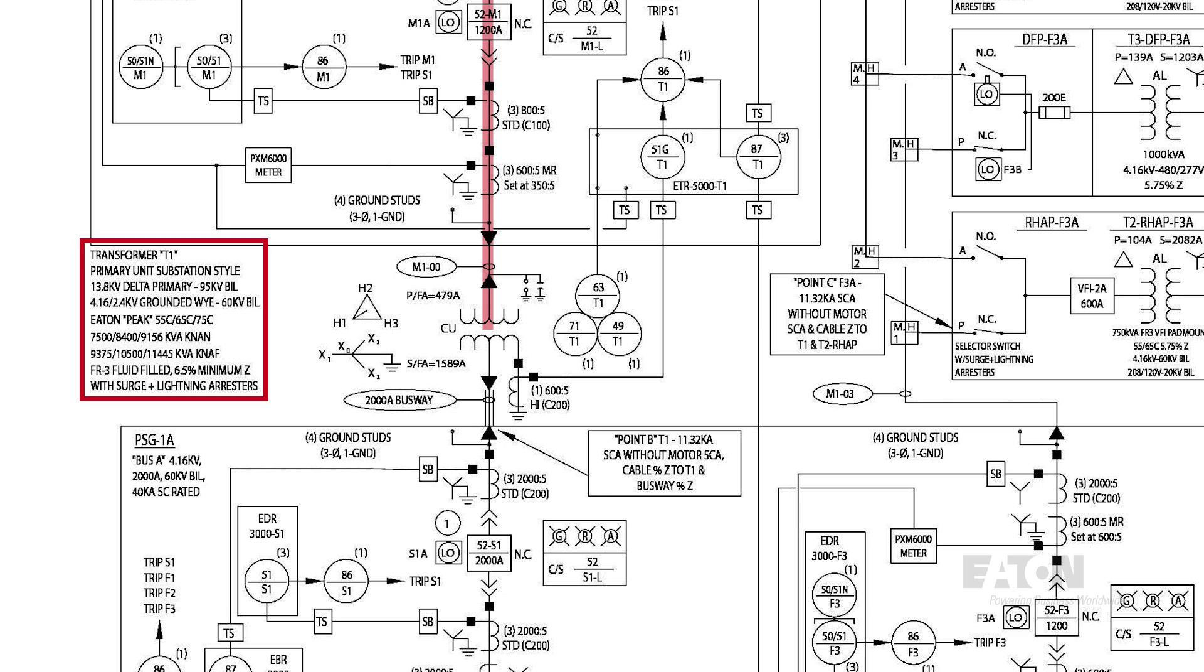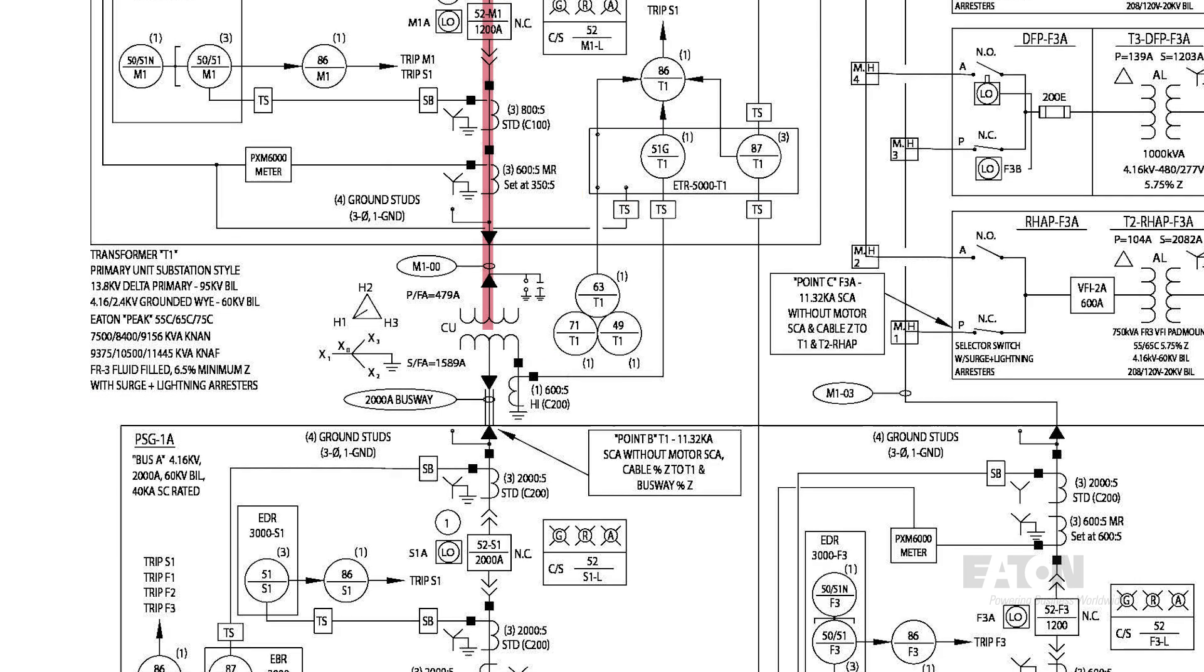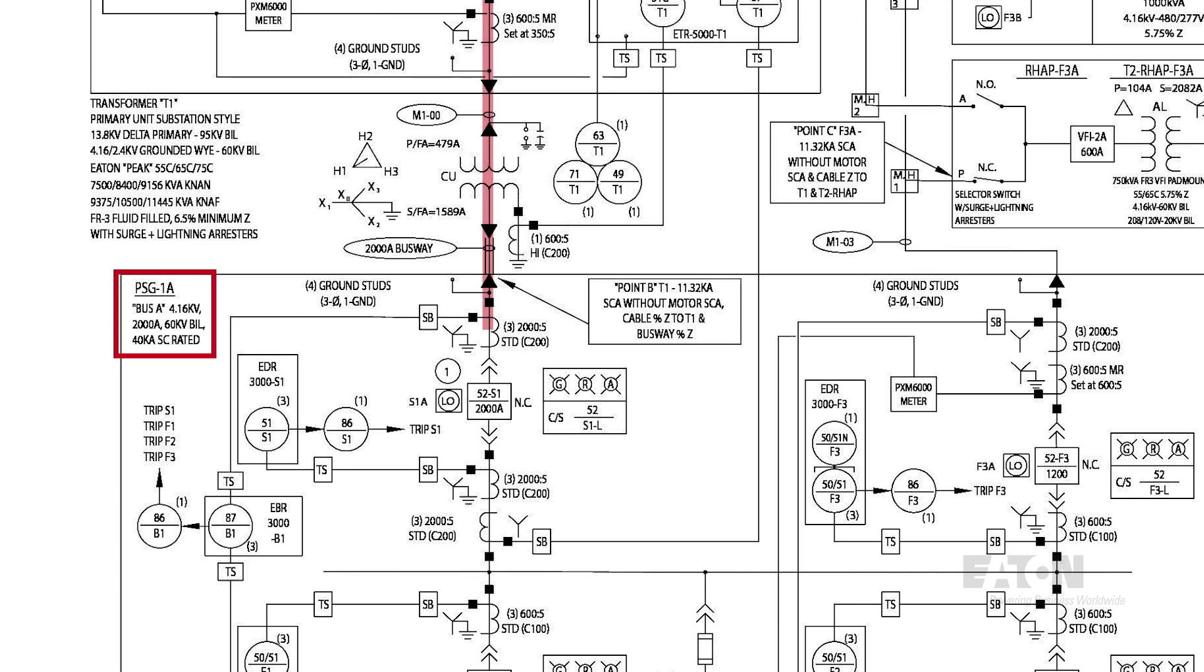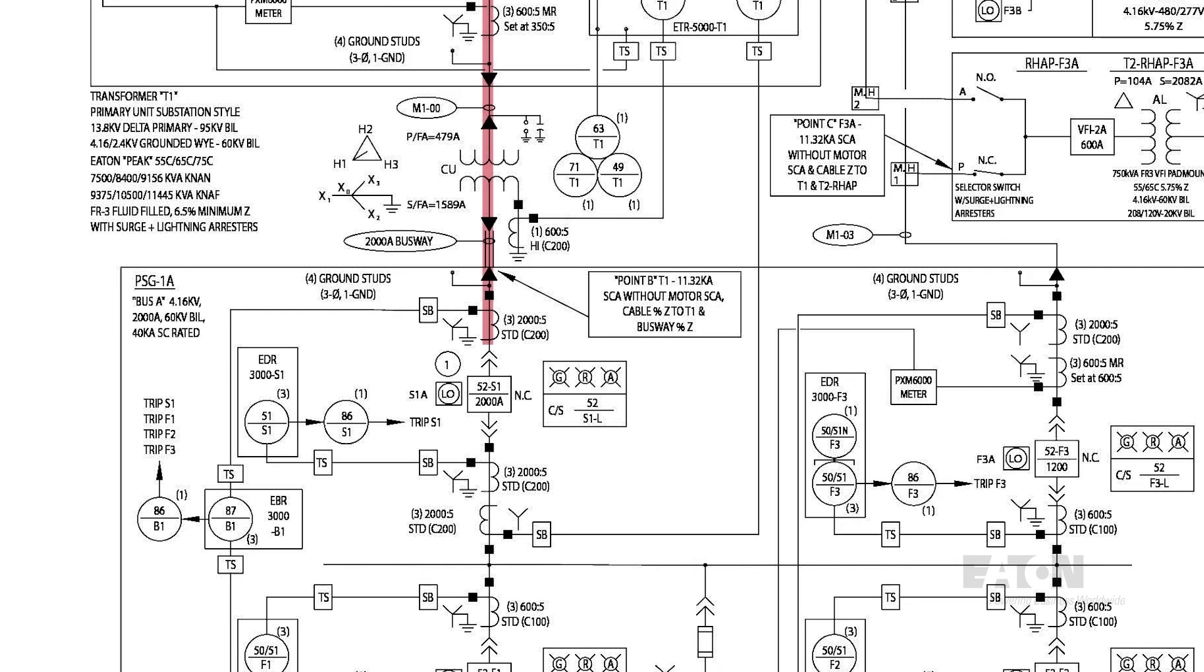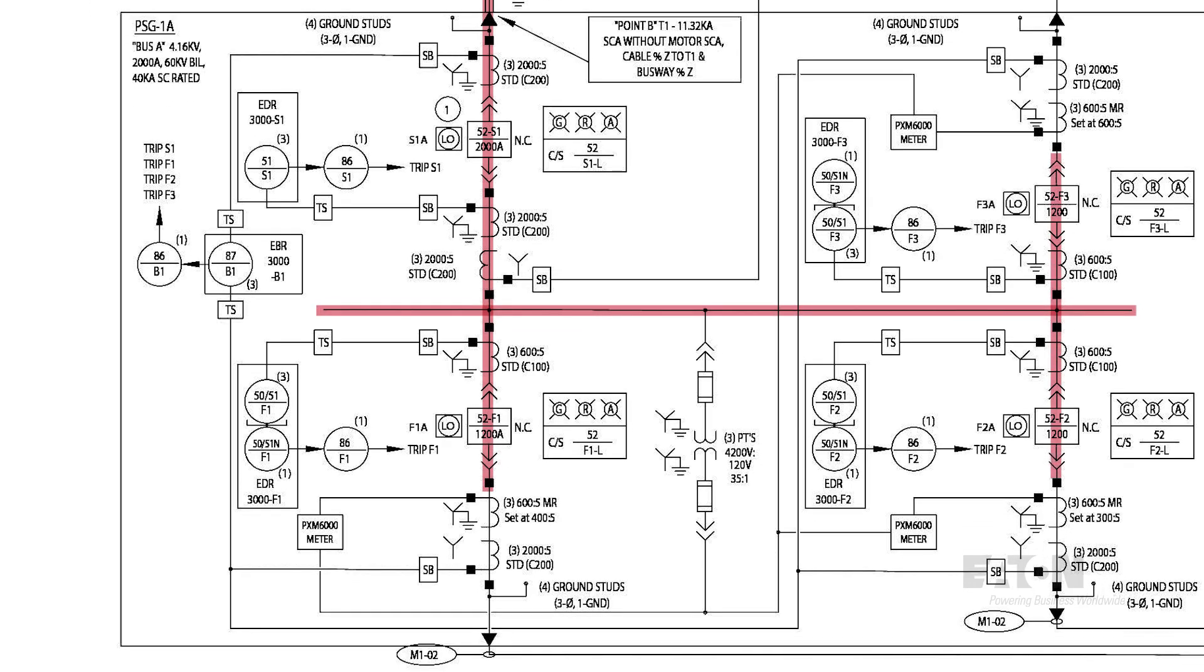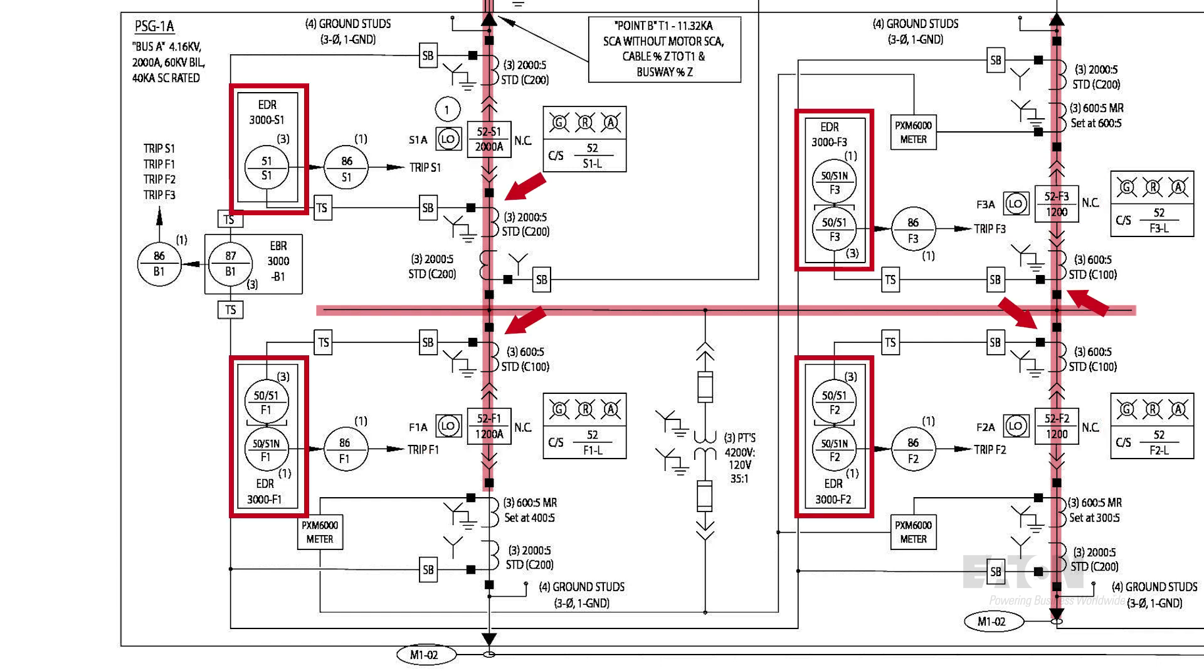Transformer T1 is 7500 kVA. It transforms the power from 13.8 kV to 4160 on the secondary side and is protected by an ETR5000 transformer protection relay via CTs on each side of the transformer. From the secondary side of transformer T1, the power flows into medium voltage switchgear lineup PSG-1A. This switchgear lineup is 4160 and has 2000 amp bus. You can see there are several different breakers in this lineup. It's larger than the 13.8 kV lineup upstream as it includes a main breaker labeled 52-S1 and three feeder breakers labeled 52-F1, F2, and F3.